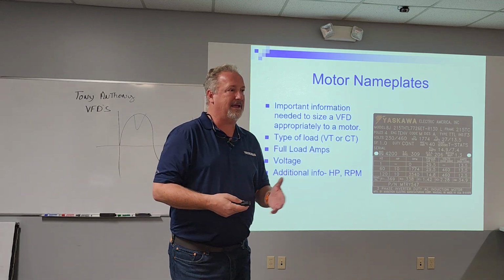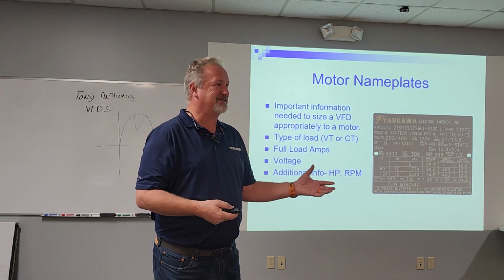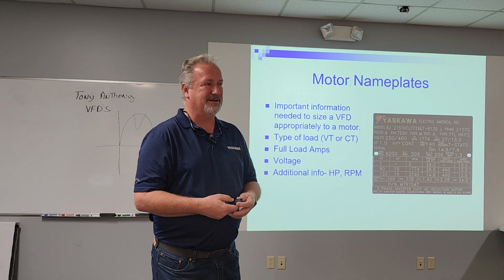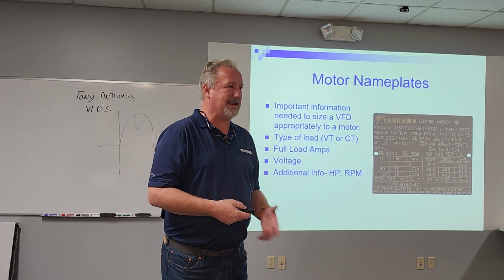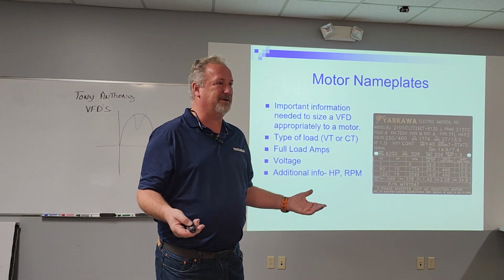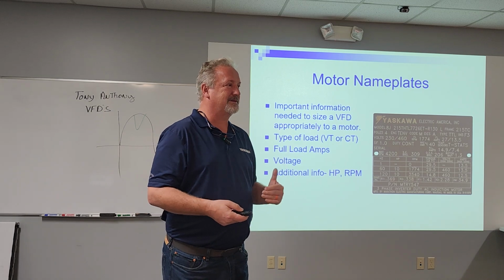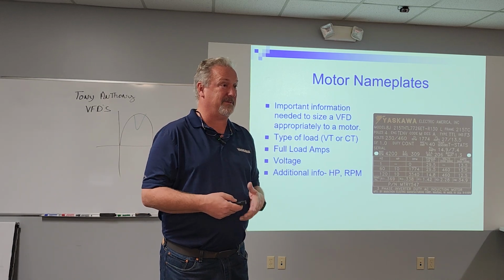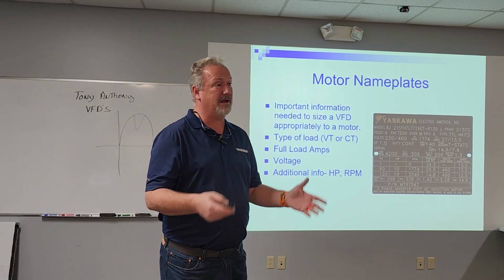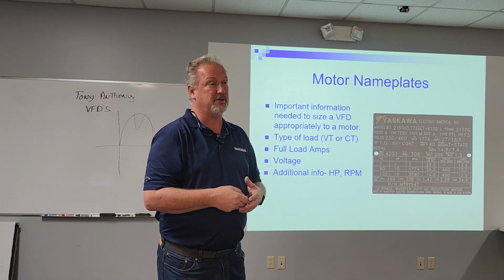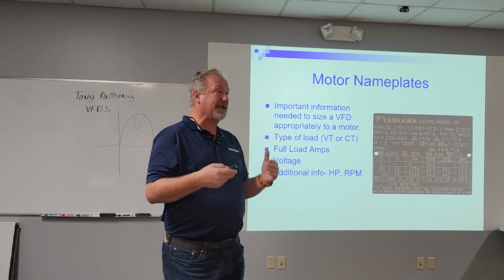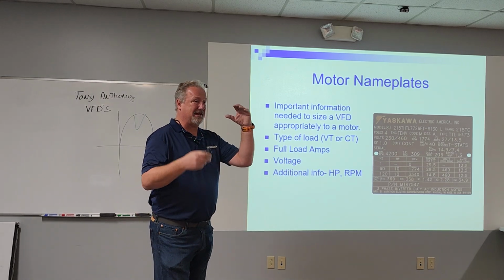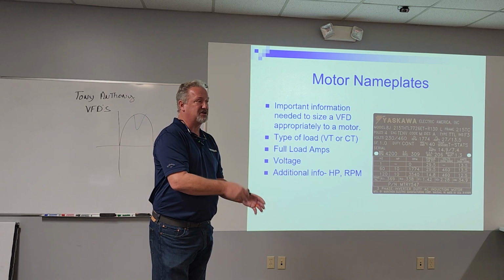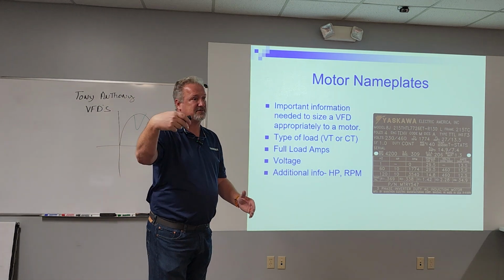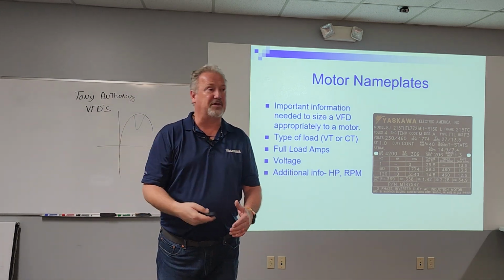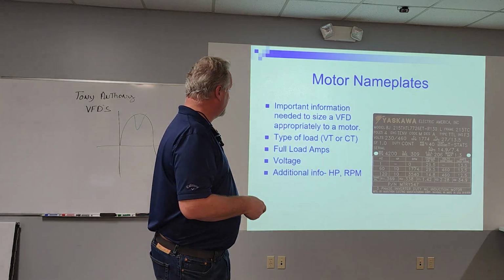What if you have an 8-pole, high torque motor? A 20 horsepower 8-pole high torque motor is going to draw more amps than an 1800 RPM motor. A 900 RPM motor has more torque and it's going to draw more current. You can get yourself in a situation where, with certain motors, you may need to oversize the drive by at least one size, sometimes. So that's why the full load amps are the most important thing.